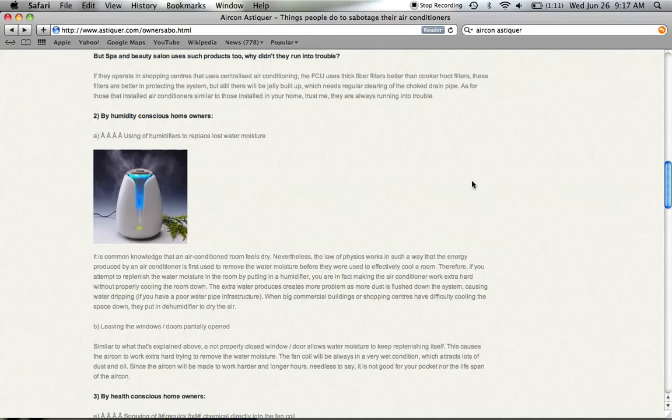The fan coil becomes even cooler, and because of that, the air becomes even drier. So in fact, the best thing you can do is to clean up your aircon. Make sure that it's properly clean. It's not those general servicing, because general servicing is just so superficial. It's not effective, and a proper cleaning improves the heat exchange and the flow rate of the aircon, which is what is needed to address a dry room condition.